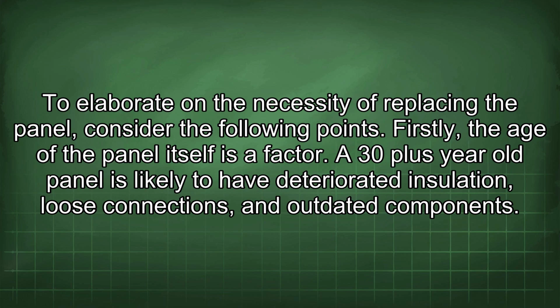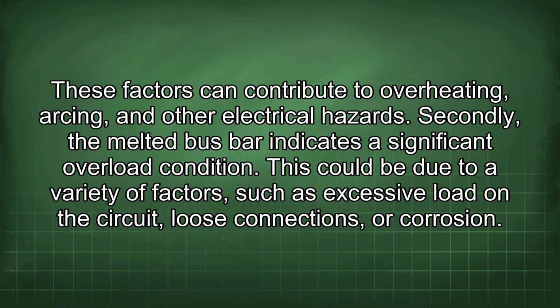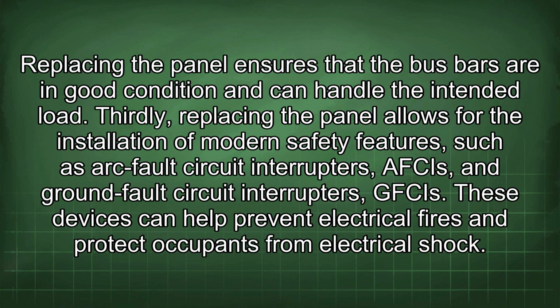Firstly, the age of the panel itself is a factor. A 30-plus-year-old panel is likely to have deteriorated insulation, loose connections, and outdated components. These factors can contribute to overheating, arcing, and other electrical hazards. Secondly, the melted bus bar indicates a significant overload condition. This could be due to a variety of factors, such as excessive load on the circuit, loose connections, or corrosion. Replacing the panel ensures that the bus bars are in good condition and can handle the intended load.